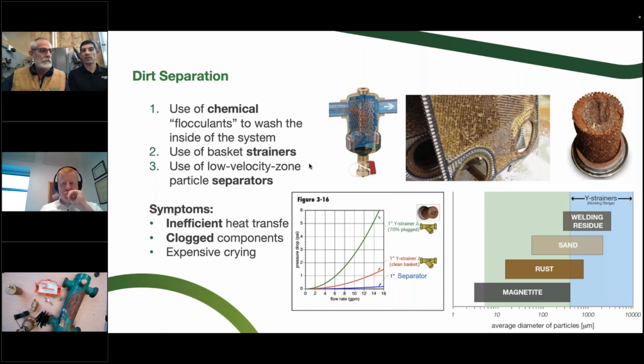And you're going to get stuff down to like the diameter of your hair with the dirt separator. Maybe not on the first pass, it might be on the second or third or 10th pass that you get those little particles, but you're going to get smaller stuff than what you would get with a Y strainer, kind of showed in the bottom right corner here, down to smaller grains of sand and rust. And then magnetite will be kind of the next thing that we talk about, that we actually have to have a third protection method with magnetite.